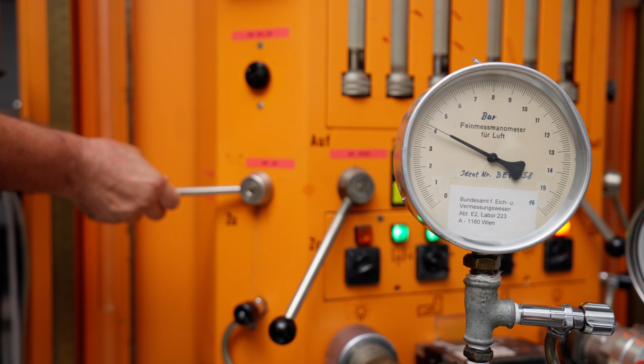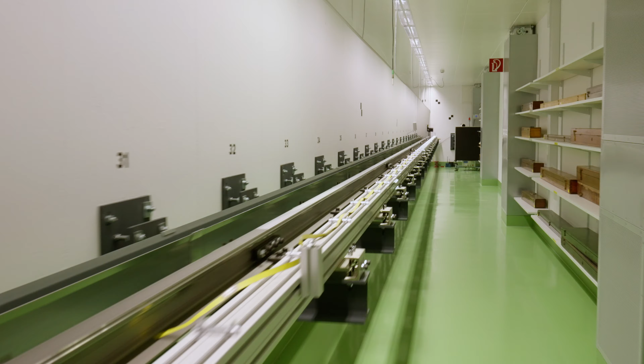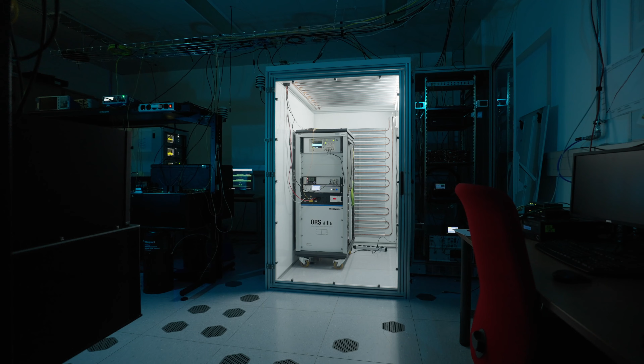The basis of metrology is the international system of units with its 7 base units and the derived units. Austrian measurement units or standards are housed in BEV's laboratories. International comparison measurements ensure that BEV's measurement standards are internationally recognized, extending the validity of calibrations based on these standards beyond national boundaries.